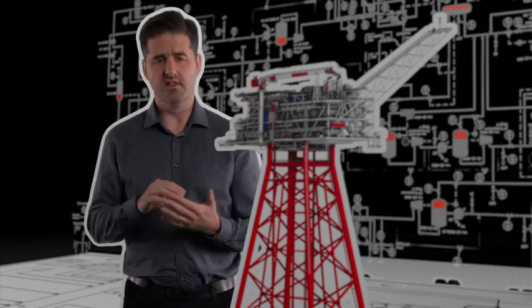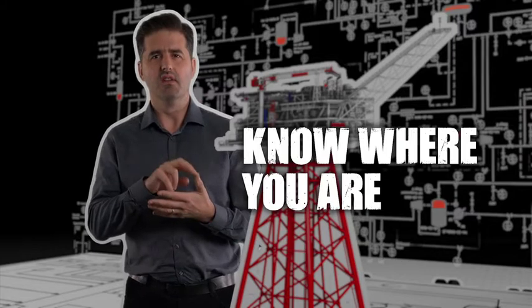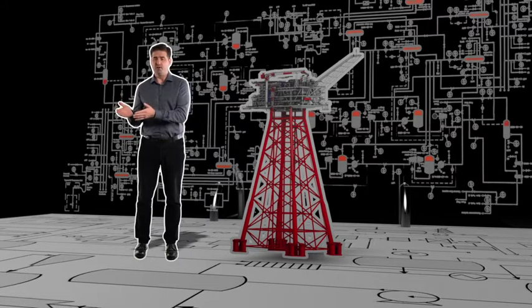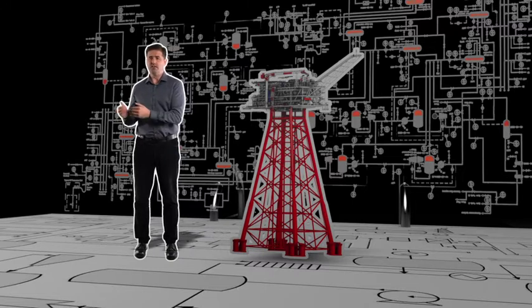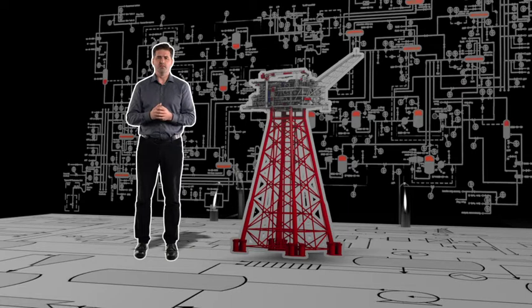The key points in that are to know where you are with respect to integrity management and being really honest about it. What we should be doing when we're trying to obtain replacement parts, say some period of time into a facility's life where the documentation may be obsolete or the parts are no longer easy to obtain: the first point is not to take a chance. It's important to check with the engineering support team about the parts that are being selected. There is no part on a facility that can't be engineered to have replacement parts.